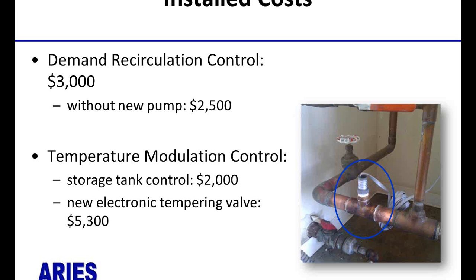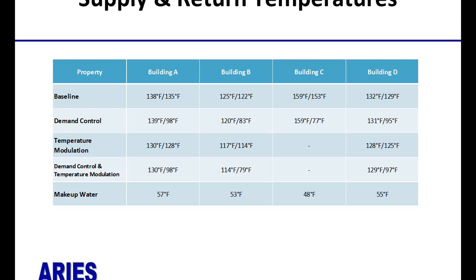So for some results. First, the installed costs. These are the actual costs at the buildings where we installed the controls. For demand recirculation, it was approximately $3,000. And for temperature modulation, it ranged from $2,000 to $5,300. If you already have an electronic tempering valve, an electronic mixing valve, on site, that can reduce the cost of temperature modulation control, obviously. And again, half of this was due to labor, and that can vary.